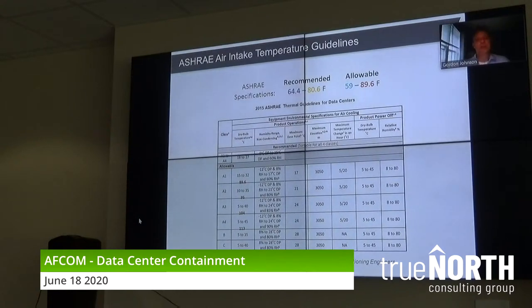But I will say this, if you have a data center from the last 5, 6, 7 years until now, you don't have A1 equipment in there. You have A2, maybe even A3 type servers. If you have a very old, 10-year-old data center, a lot of telecom equipment, it's probably A1 type equipment. And that's important because that tells us how high the temperature can go at the intake to that equipment without us shortening the life of the equipment or losing our warranty.